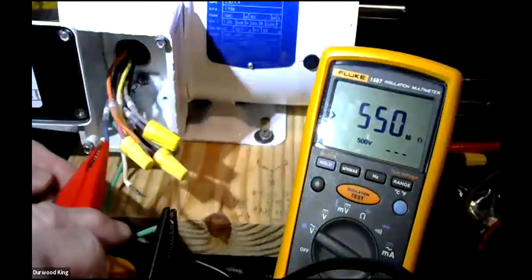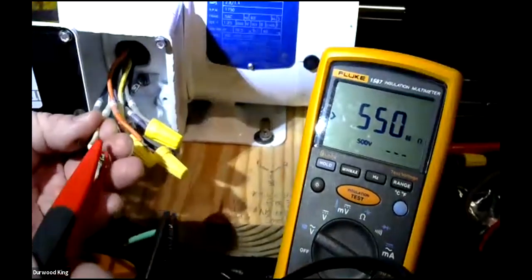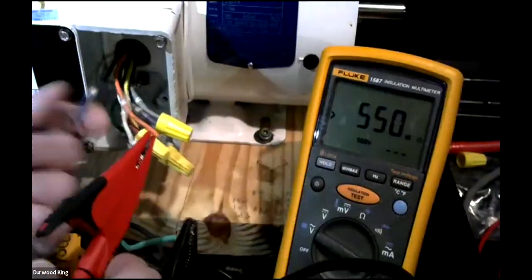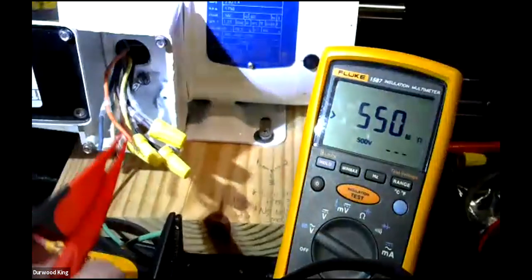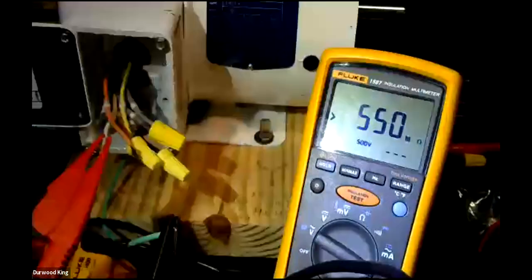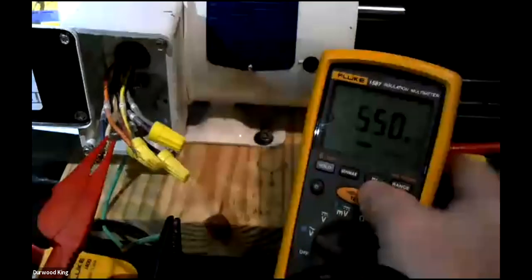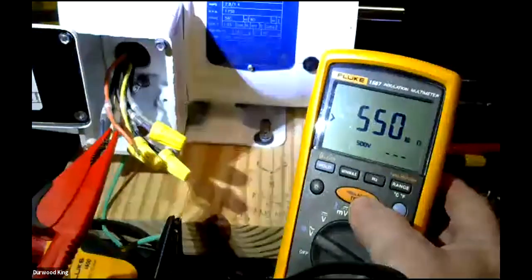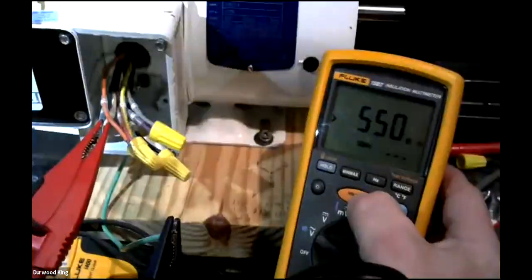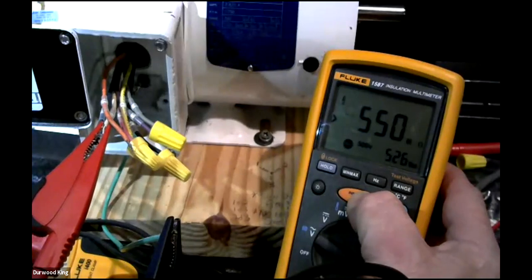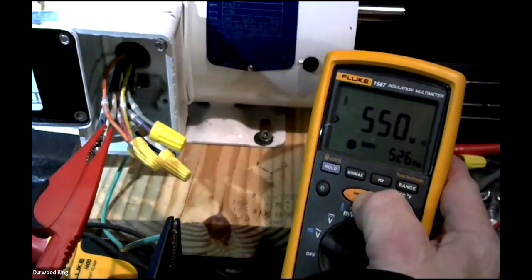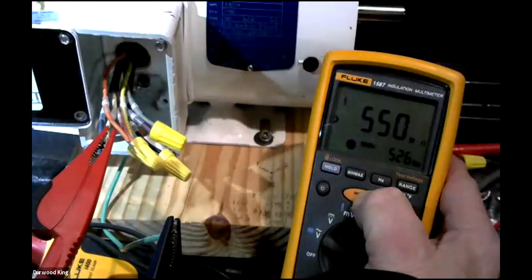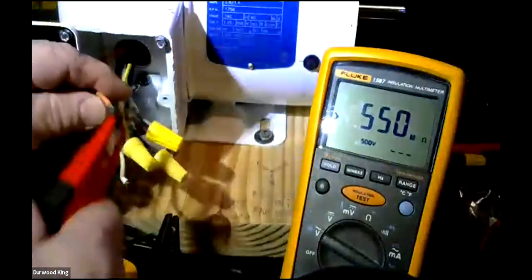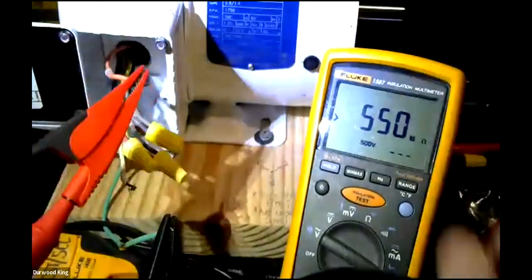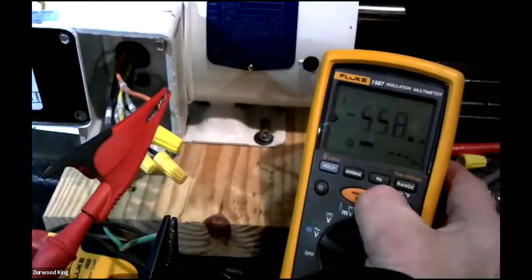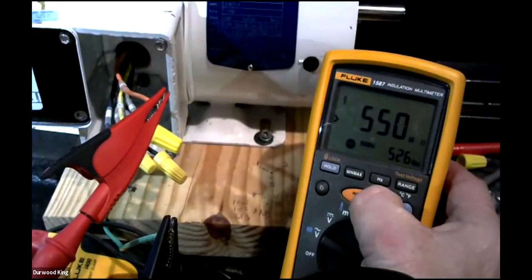Let's go to line 2. And you got to keep these leads separated. Don't let them hit each other, and don't touch them because it can light your world up if you touch them. So hit the button. Greater than 550 meg, so that's considered good. If you're over 1 meg, you're okay. Okay. Let's go to 3 and hit it. And it says greater than 550.